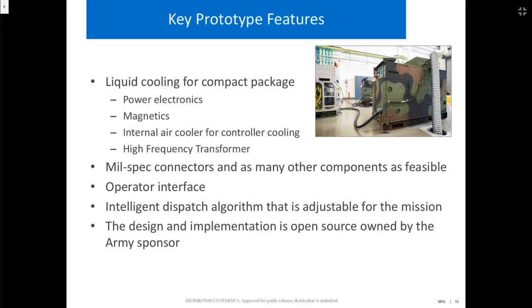We liquid cool the power electronics, and we liquid cool the magnetics using a cold plate. We also have an internal air cooler, basically an air-to-liquid heat exchanger, and liquid cooling to the high frequency transformer. So the major heat-generating components and the overall internal air of this thing are all dumped to a liquid cool system that's outside the unit.